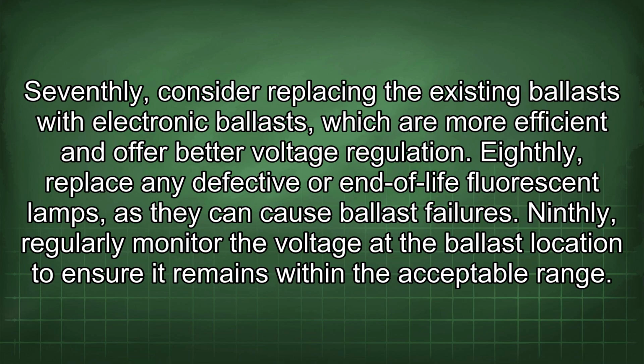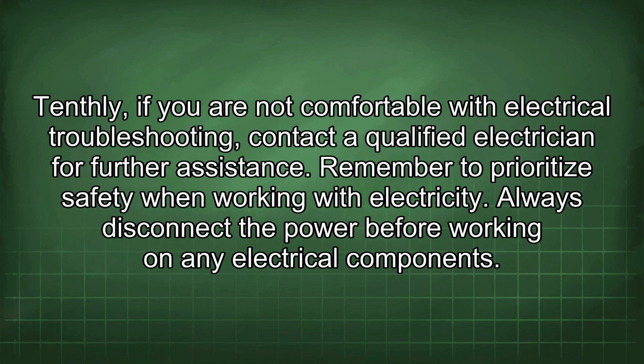Seventhly, consider replacing the existing ballasts with electronic ballasts, which are more efficient and offer better voltage regulation. Eighthly, replace any defective or end-of-life fluorescent lamps, as they can cause ballast failures. Ninthly, regularly monitor the voltage at the ballast location to ensure it remains within the acceptable range. Tenthly, if you are not comfortable with electrical troubleshooting, contact a qualified electrician for further assistance.